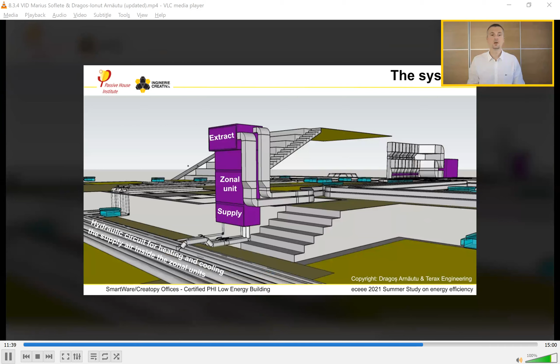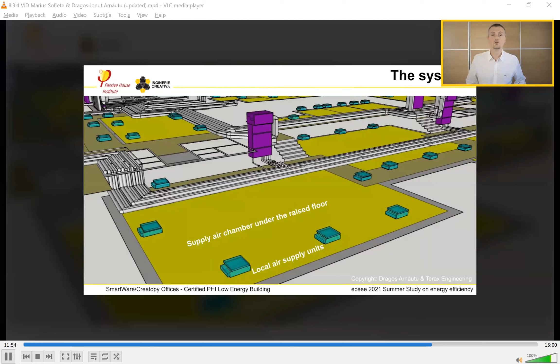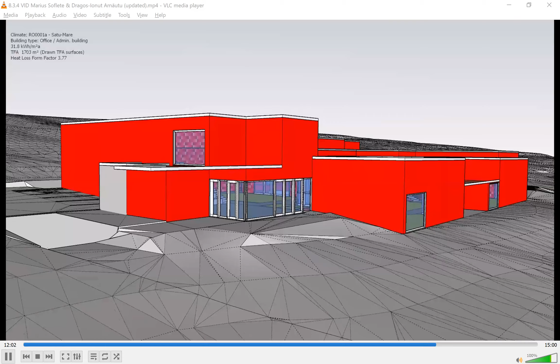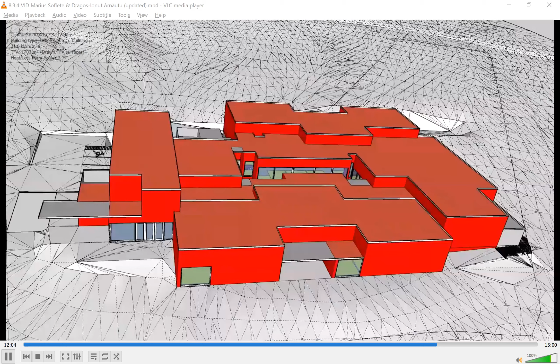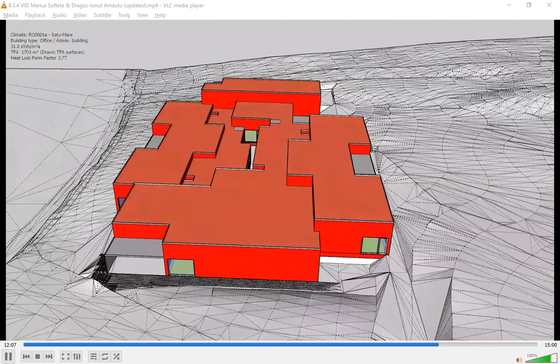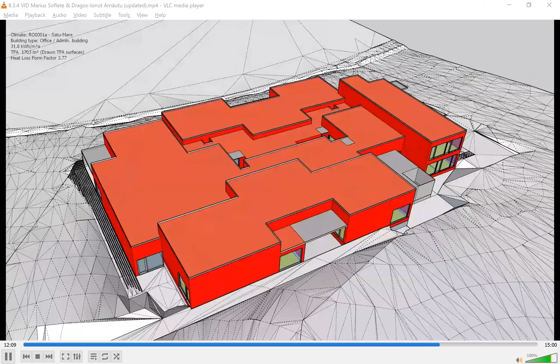The zonal units extract the air at the top, also connected with the energy recovery ventilation unit, and supply fresh and reconditioned air at the bottom, under the entire floor area of each specific zone towards the local units. The local units supply air to the rooms from under the raised floor and are able to locally regulate the temperature and airflow according to the loads of each zone and user needs. They are provided with temperature sensors, dampers and centrifugal fans. Local units and zone units are integrated into the building's management system for centralized control and optimized energy consumption.